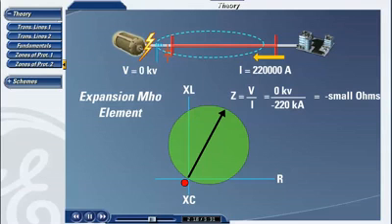To make sure that the MHO characteristic does not mistake this as being an internal fault, the relay recognizes the low impedance of the line, sees that the value is negative, and expands the radius of the circle. Since the MHO circle is no longer near the origin and the location of the fault, there is no chance of the relay false tripping. Notice, however, that the reach of the MHO circle did not change and still extends out to the end of the original zone of protection.